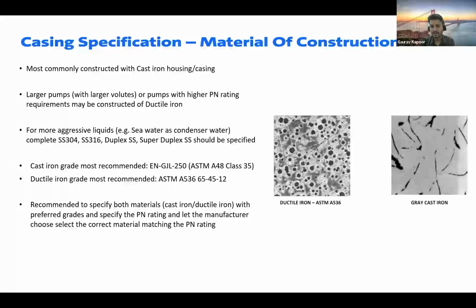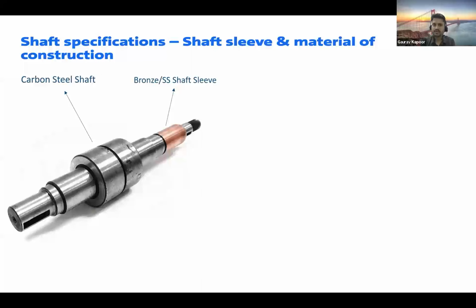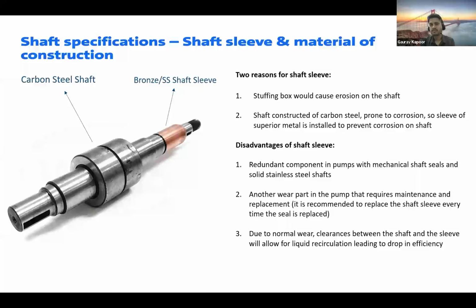Now, one of the main important factors to understand in today's presentation is shaft sleeve and material of construction. A few years before, the shaft sleeve was a mandatory design parameter, because at that time the shafts were constructed of carbon steel, which were very prone to corrosion. To avoid corrosion, we were using a superior metal, bronze or stainless steel, as a shaft sleeve. But the disadvantage of using a shaft sleeve is that there was an extra component in the machine which would wear and you have to replace it, and to replace it you have to open up the complete pump and take off the shaft and bearing.